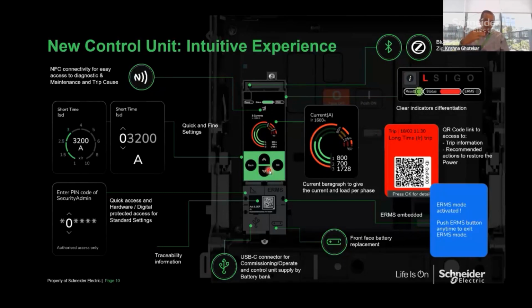So to make it much more efficient, what we have done is the test port of a breaker is made simpler. We have gone with USB-C type, which is a standard connector which we use with our smartphone or many other tabs and other devices. So this USB-C is there as a test port for the breaker. That means you don't need a special cable, you don't need a special testing kit. You just connect your USB cable to the trip unit and to your laptop.